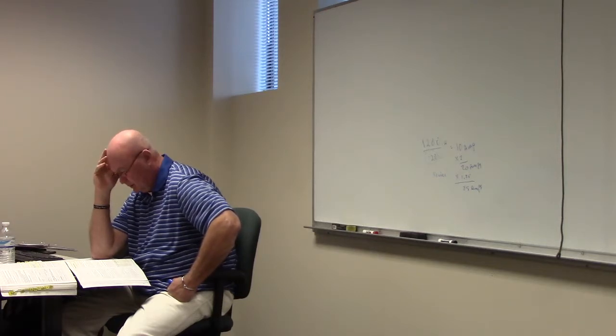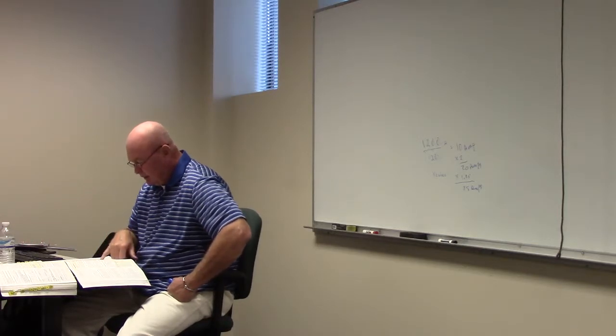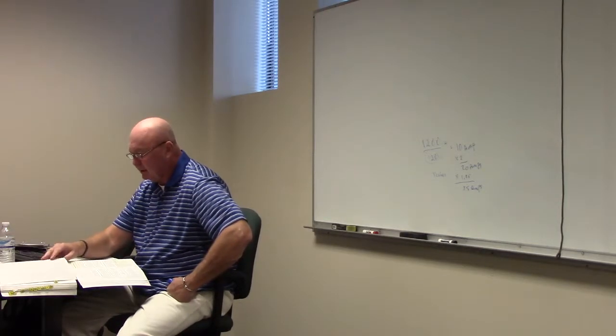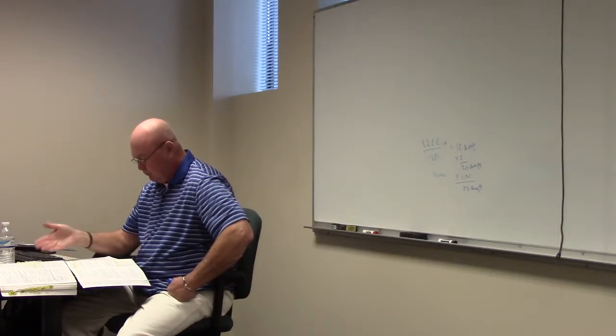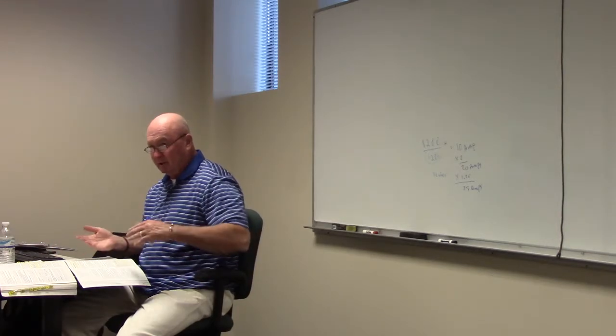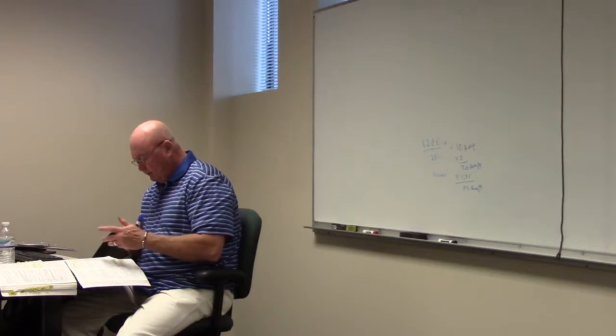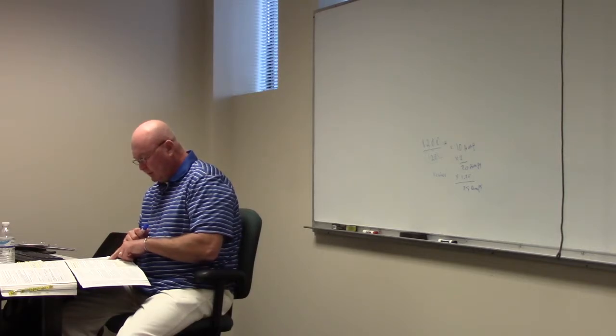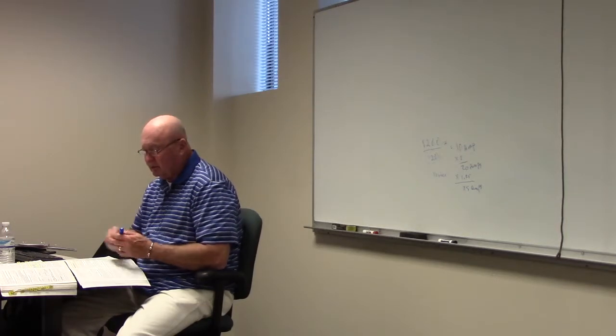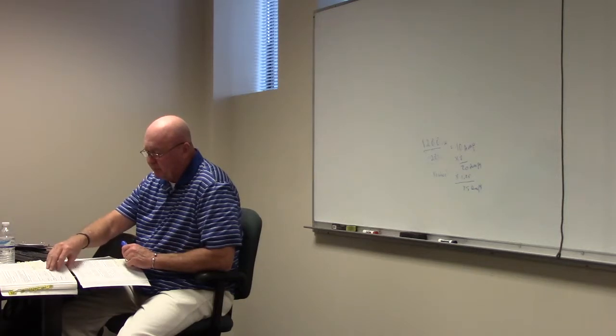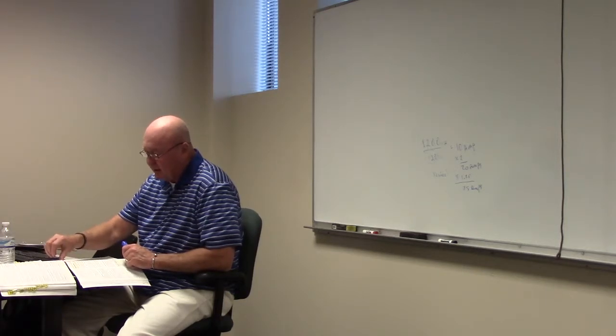Number 2? Good. And if you notice in the book, that would also be the same size that we could use for the neutral, because we only had a load of like 60. And we don't want the neutral to be any smaller than the ground, right? So it says here that we would use that, okay? The fuses, and if you read on, I'm reading on page 35, the fuses selected in the NEC rules for motor feeder protection. The ungrounded conductors therefore are protected at 300 amps each, because if we go to, let's go to 240.6(A).